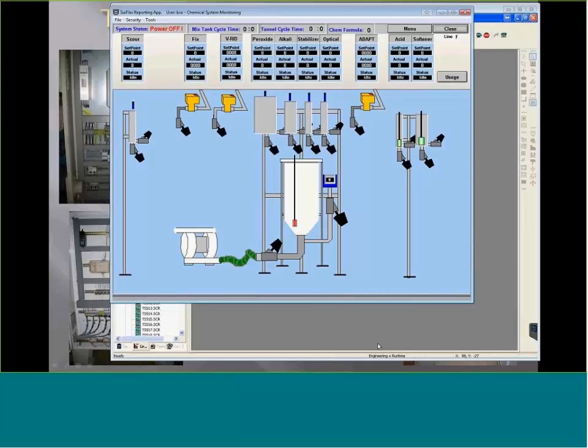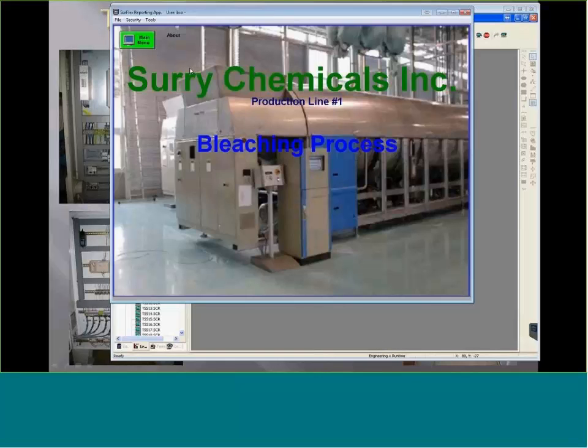a lot of our chemicals are either thick, or sticky, whatever the reason. The owner, the boss, doesn't allow any movable parts to come in contact with the chemicals. Anything that does come in contact with chemical has to be stainless steel. So any kind of measuring device cannot have any movable parts. So paddle wheels are out of the question. And so these meters here you see are Coriolis meters, if I pronounce that right, and all the valves are stainless steel.